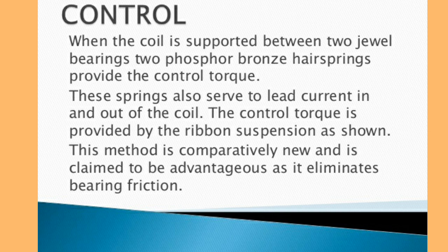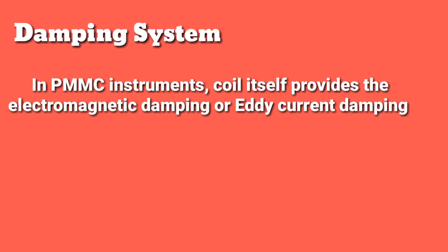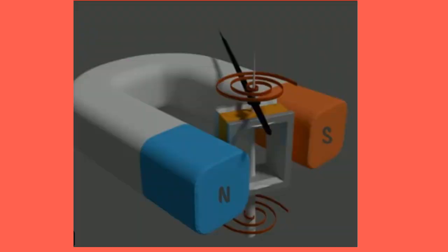Every instrument requires a deflecting torque, a controlling torque, and a damping torque. The deflecting torque is produced in the coil, the controlling torque is produced by the controlling spring, and the damping system reduces oscillation. The damping torque keeps the movement of the coil at rest, and it is induced because of the movement of the aluminum core moving between the poles of the permanent magnet.